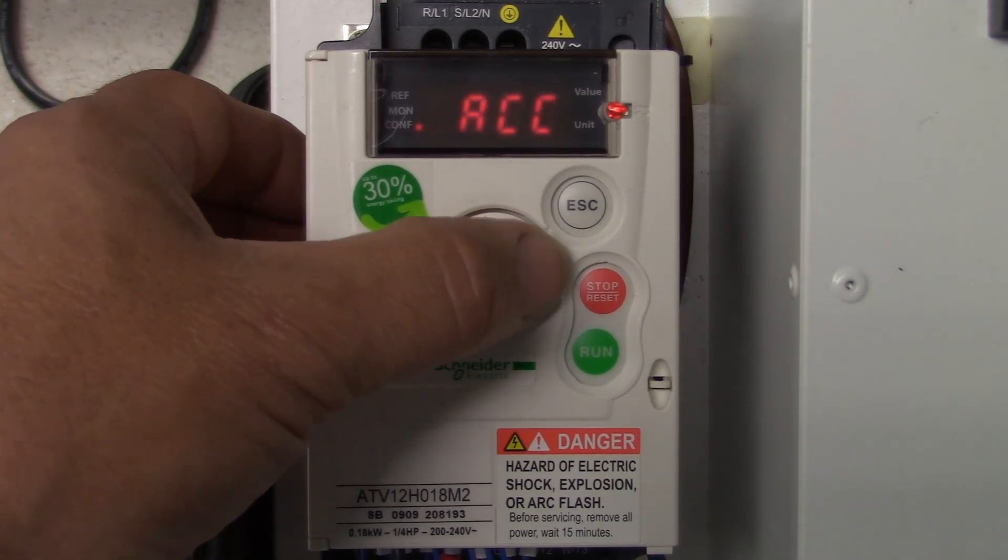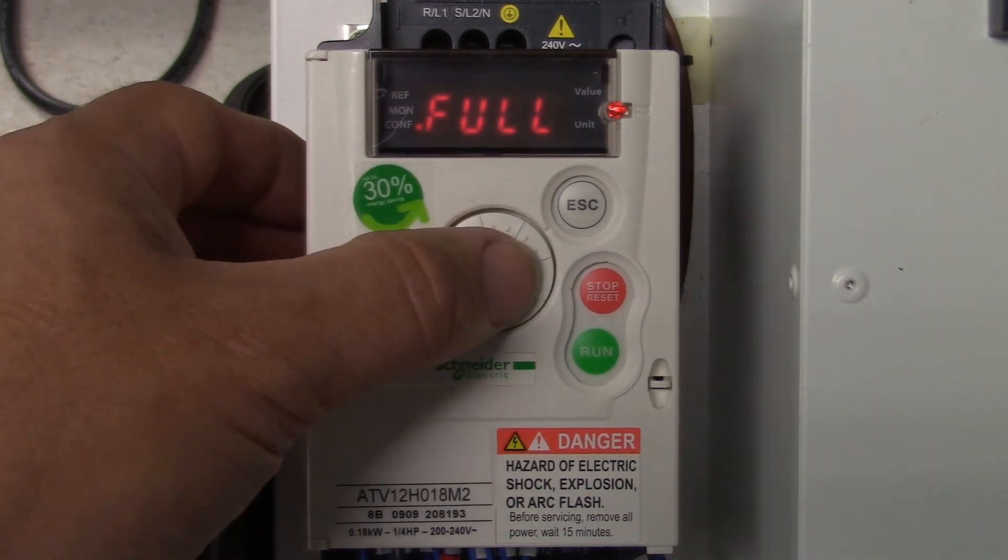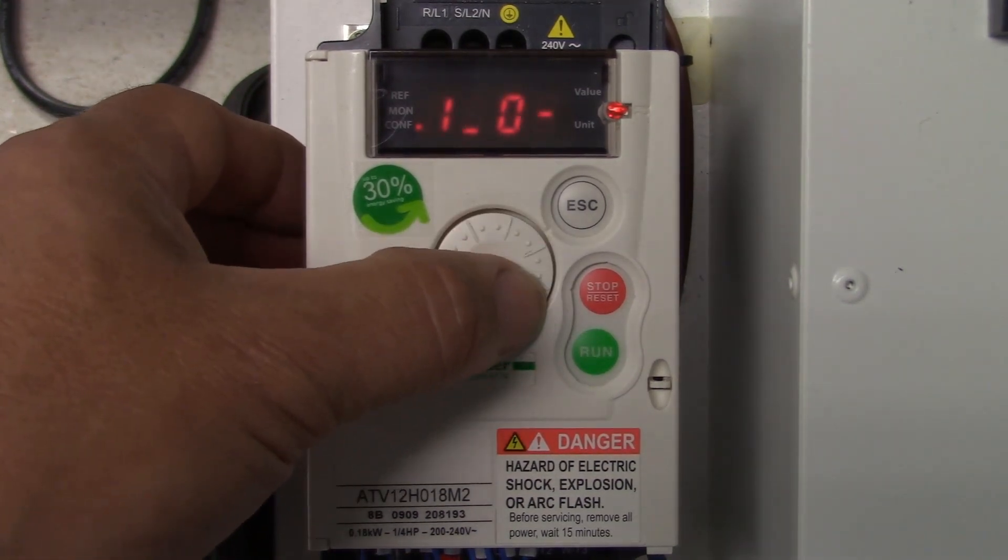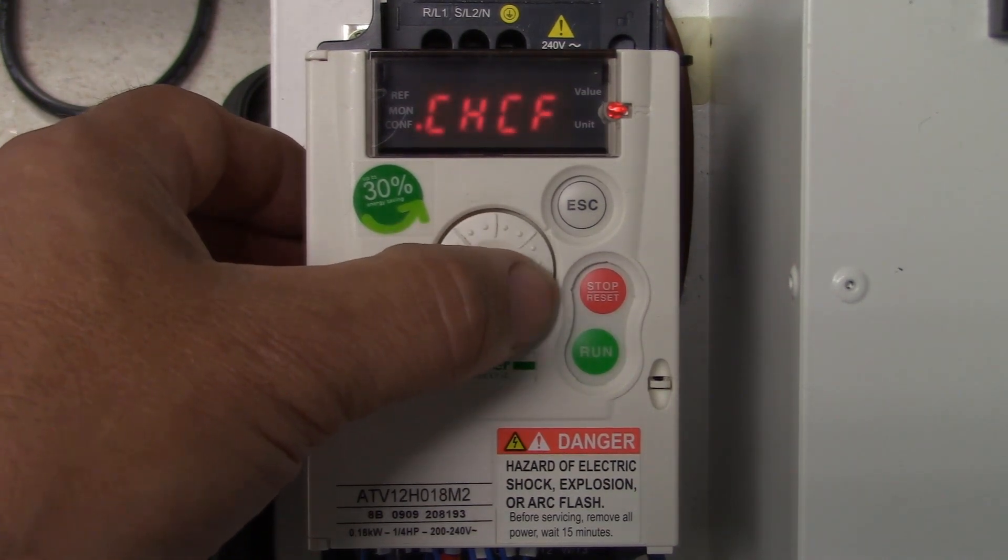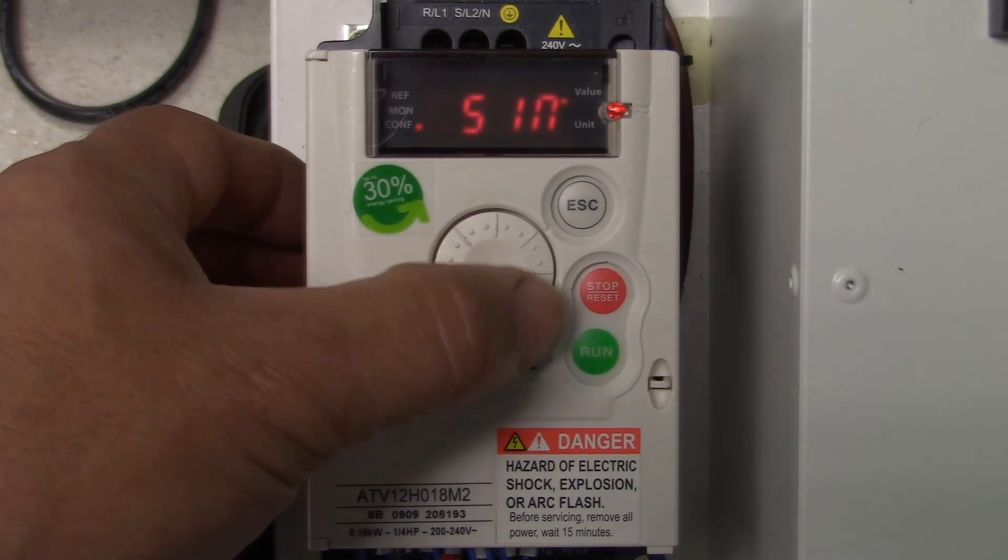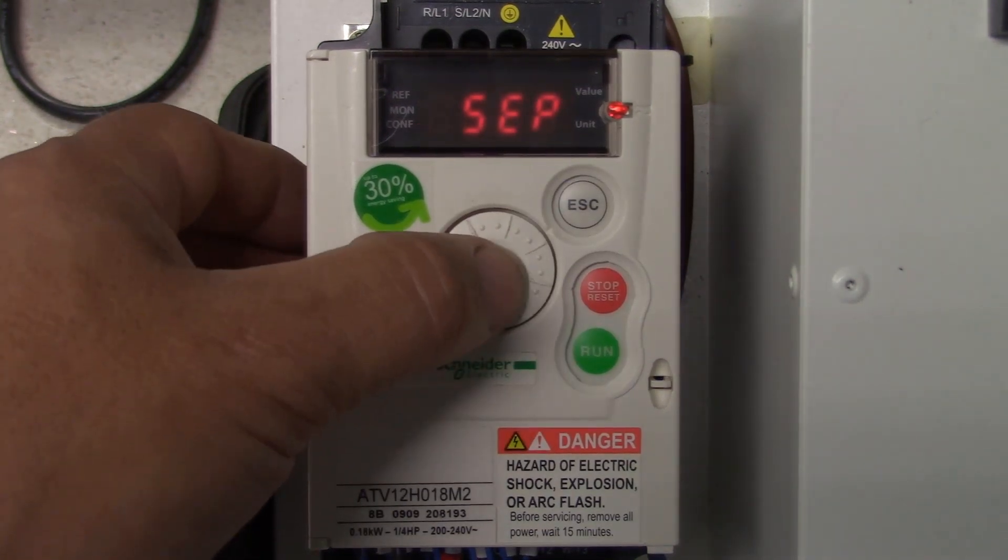This is because the reference and the command has not been separated in the CTL menu. You need to go back to the CTL menu and change parameter CHCF to separate. This will separate where the drive looks for its reference with regards to where the command comes from.